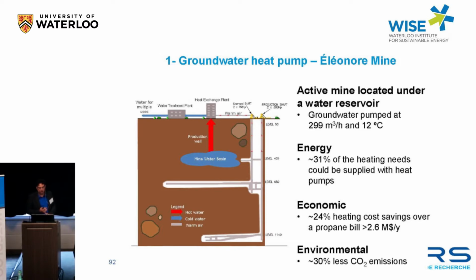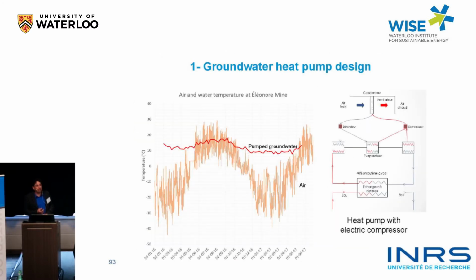rate, more than about 300 cubic meters per hour, since the mine is located under a hydroelectric water reservoir. So there's lots of water infiltration in the mine. And we believe this water could be used with geothermal heat pumps to produce heat and decrease the energy demand to heat the underground working. The mine actually has access to cheap hydroelectricity, but still uses propane to heat the underground working to decrease its peak load. So how could that be implemented?